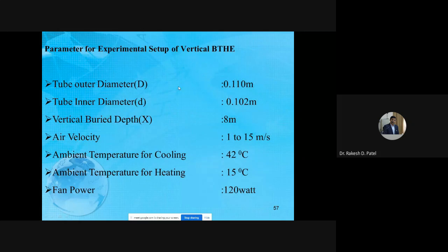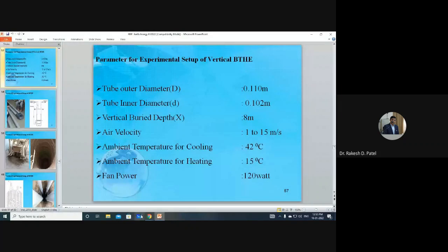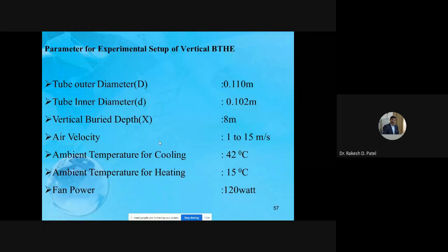Now, these are the parameters for the vertical heat exchanger. The tube outer diameter is the same as the horizontal heat exchanger. Only one thing is varied, the vertical buried depth, which is 8 meter. In the horizontal buried tube heat exchanger, the buried depth is 3 meter, whereas in the vertical it is 8 meter. Air velocity is the same, 1 to 15 meter per second. So these are the parameters for the experimental setup of the vertical buried tube heat exchanger.